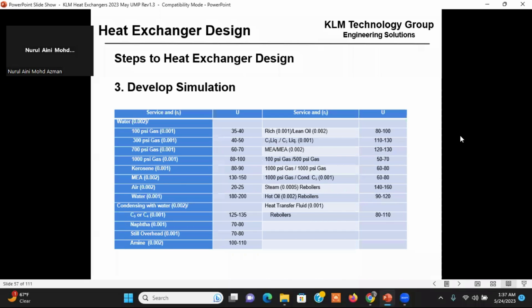All right, so you're going to pick 2 of the temperatures. You're not going to overspecify the temperatures. You're going to guess what an area is. You're going to put the U in. You're going to put the pressure drop in. You're going to converge it. If the temperature approach is good, that's a good area. If the temperature approach is high or low, you might have to add some more area to get your temperature approach down to 10 degrees. So that's kind of how you develop a simulation.